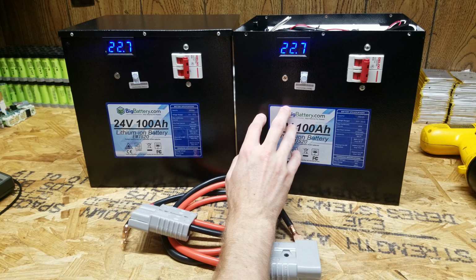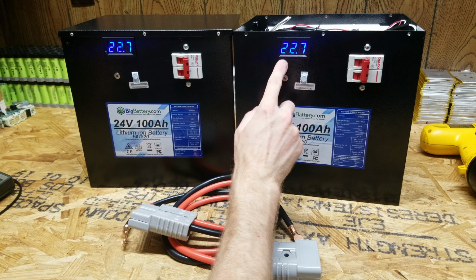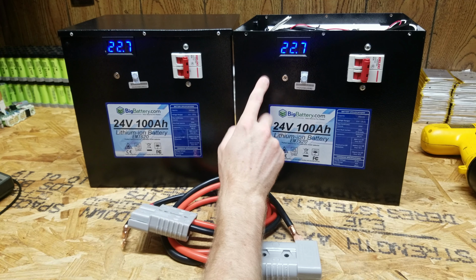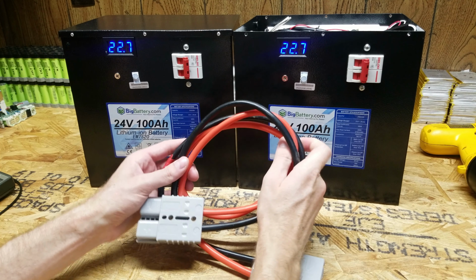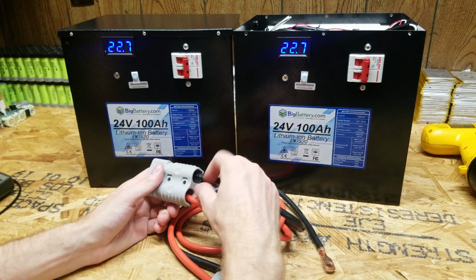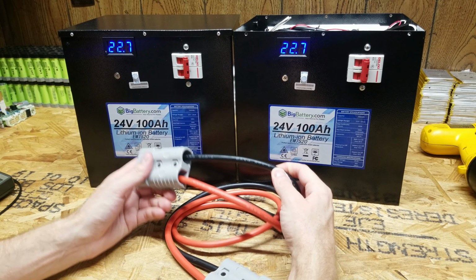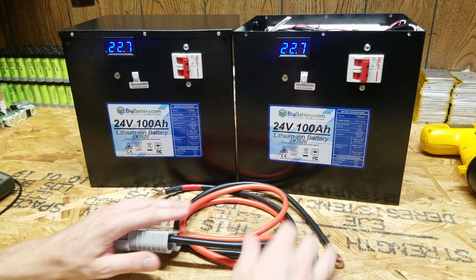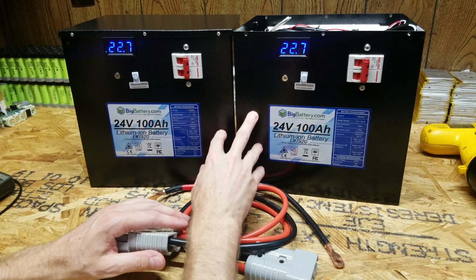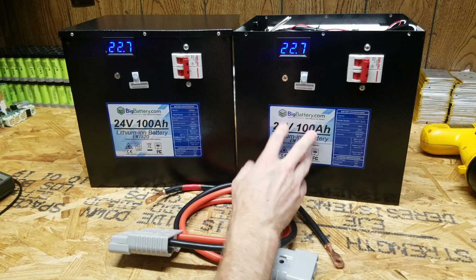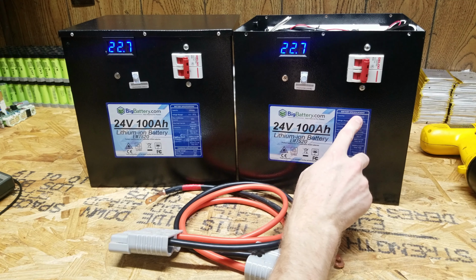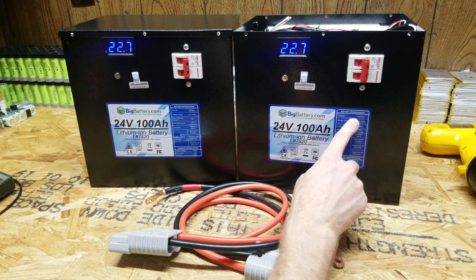And if you remember, when the inverter shut down, this voltage actually went back up by a volt in each bank. So I suspect there was a large amount of loss over these cables. But I would have preferred to see thicker than 6-gauge cable. So I'm not too concerned about the capacity. I don't doubt that if we would have done the test a little better, both on the high end and the low end, we would have gotten a little bit closer to this 2.5 kilowatt hours.